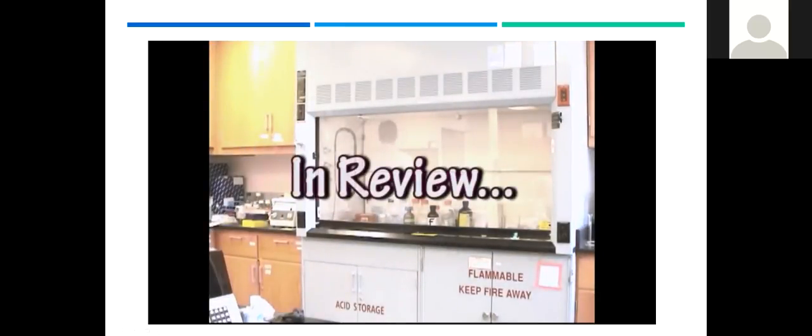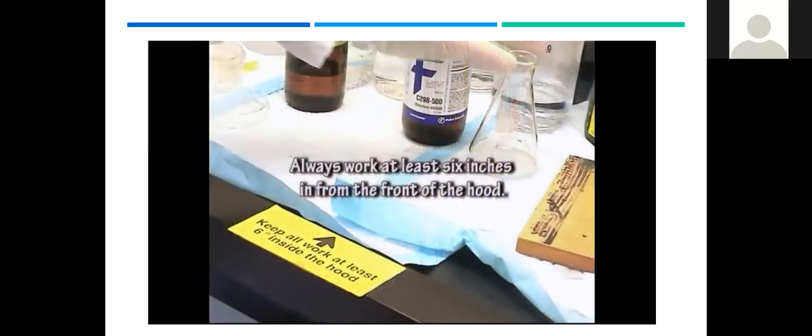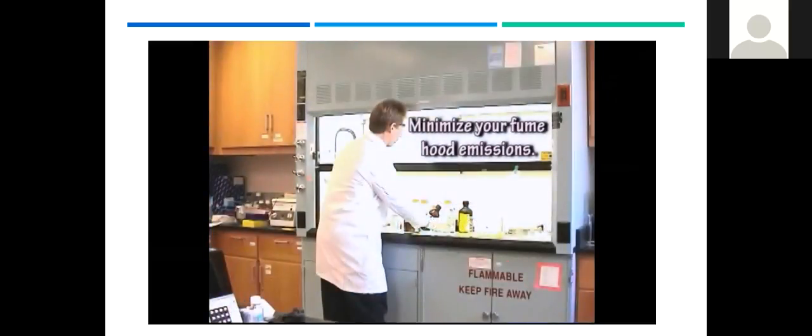In review, before using the hood, check the airflow monitor. Properly adjust the sash height. Always work at least six inches in from the front of the hood. Fume hoods exhaust into the environment. Minimize your fume hood emissions.